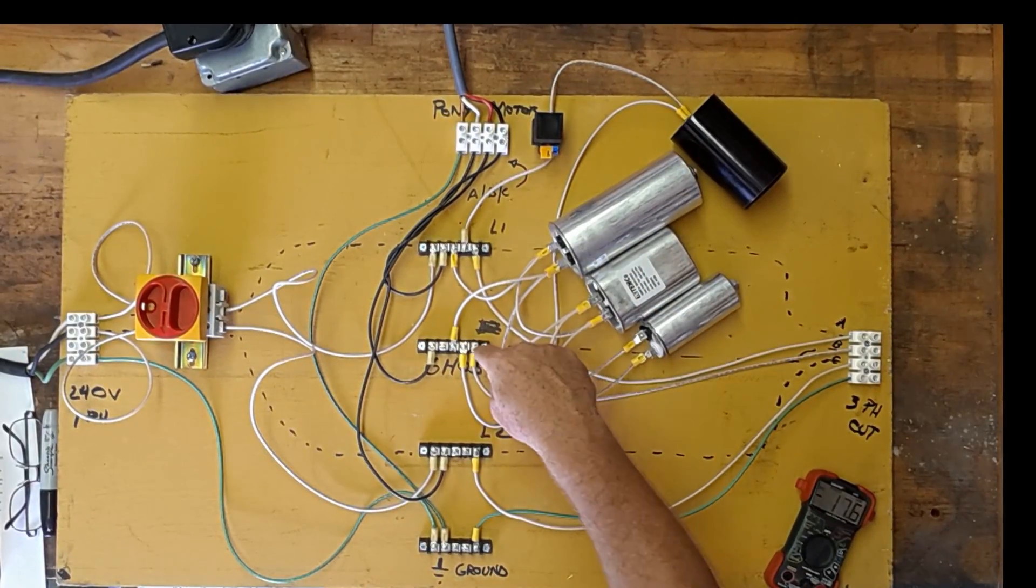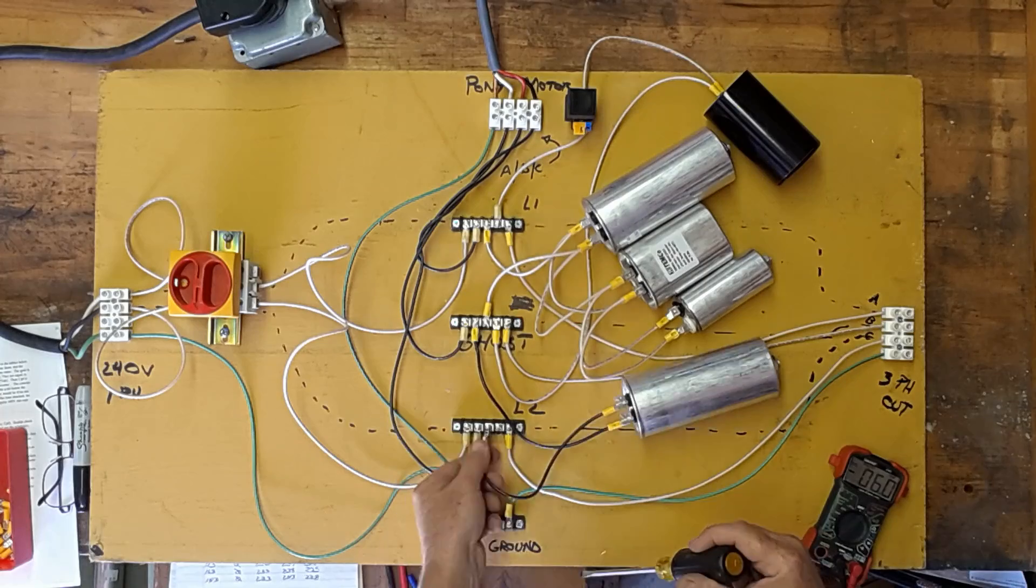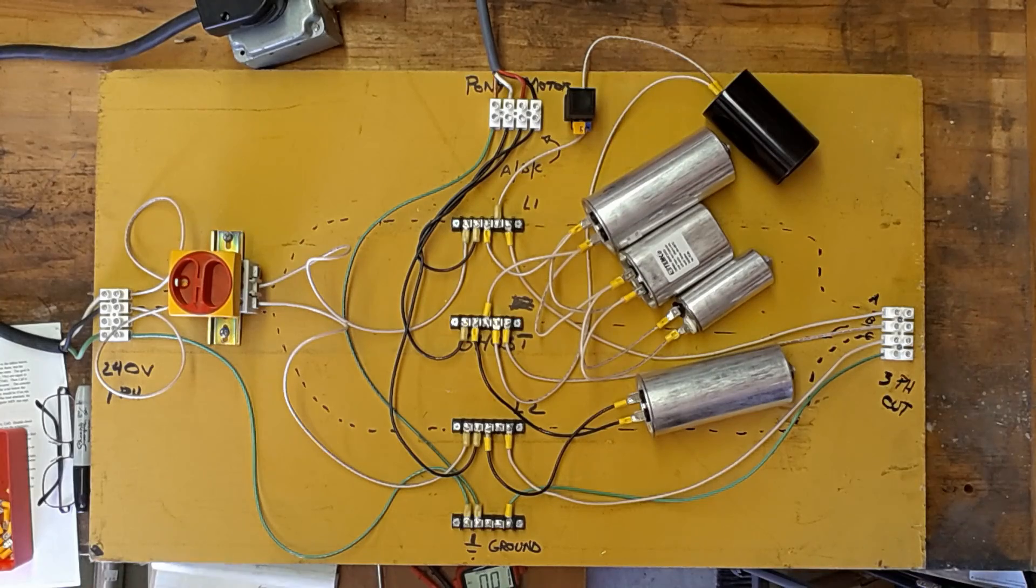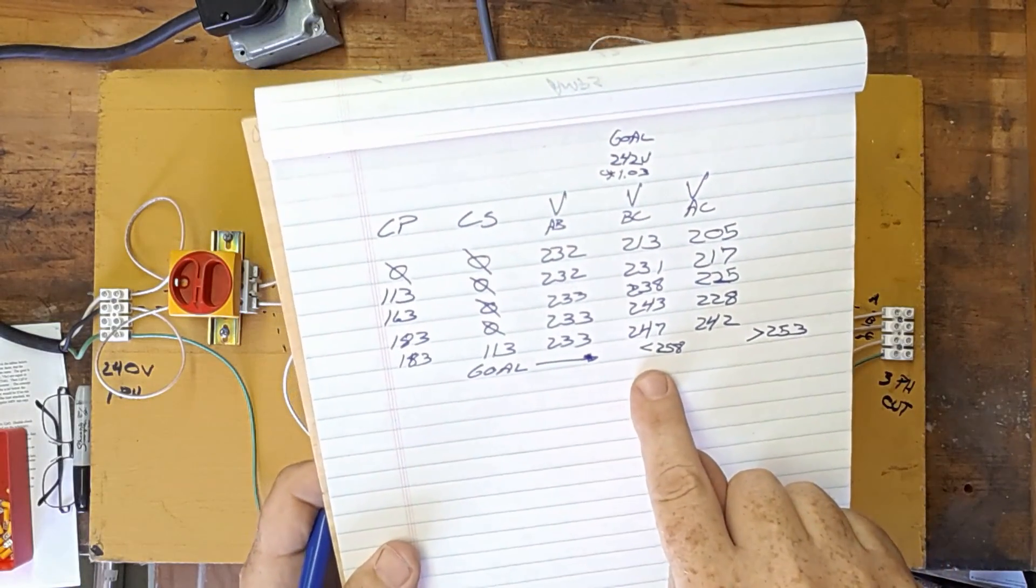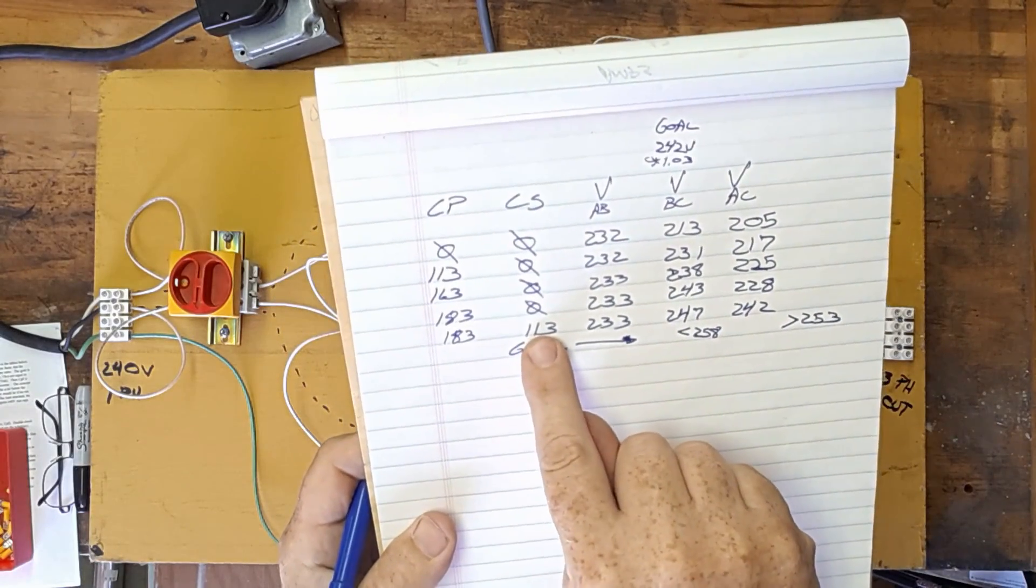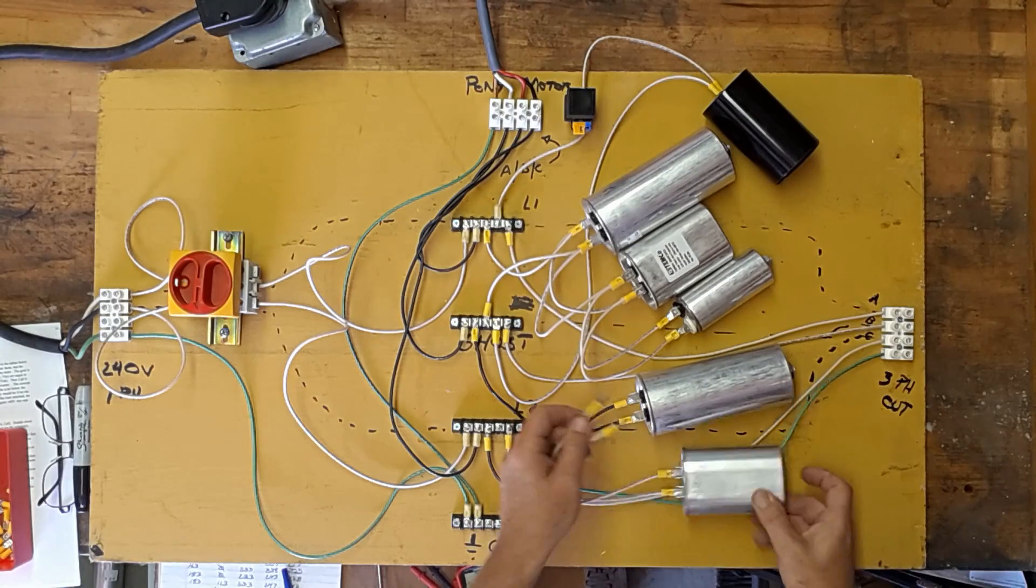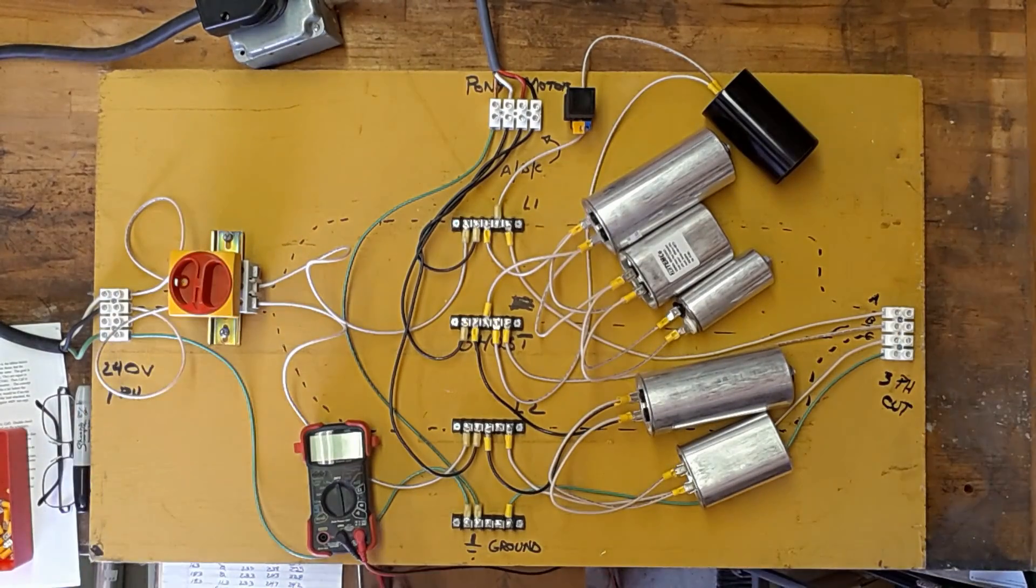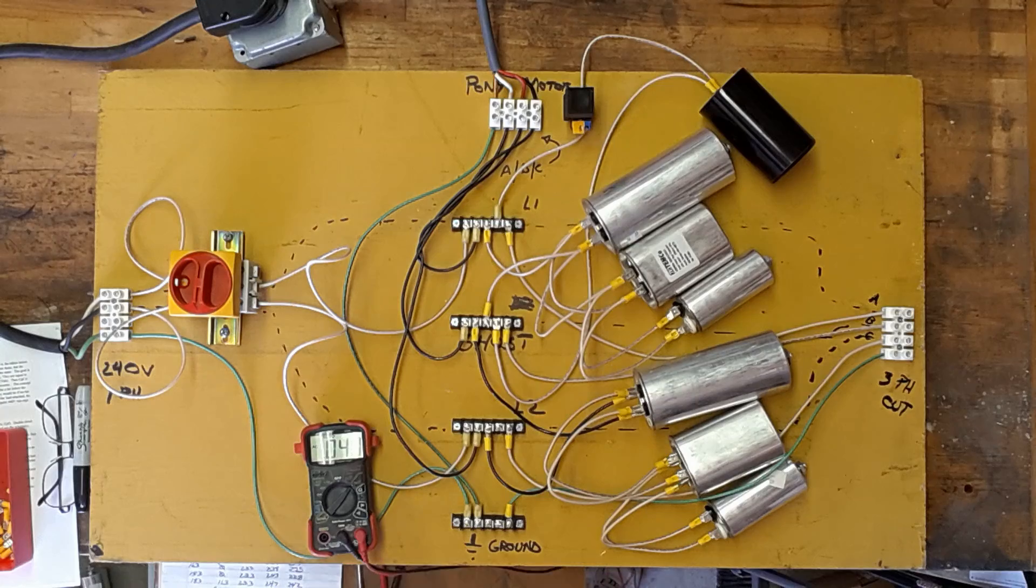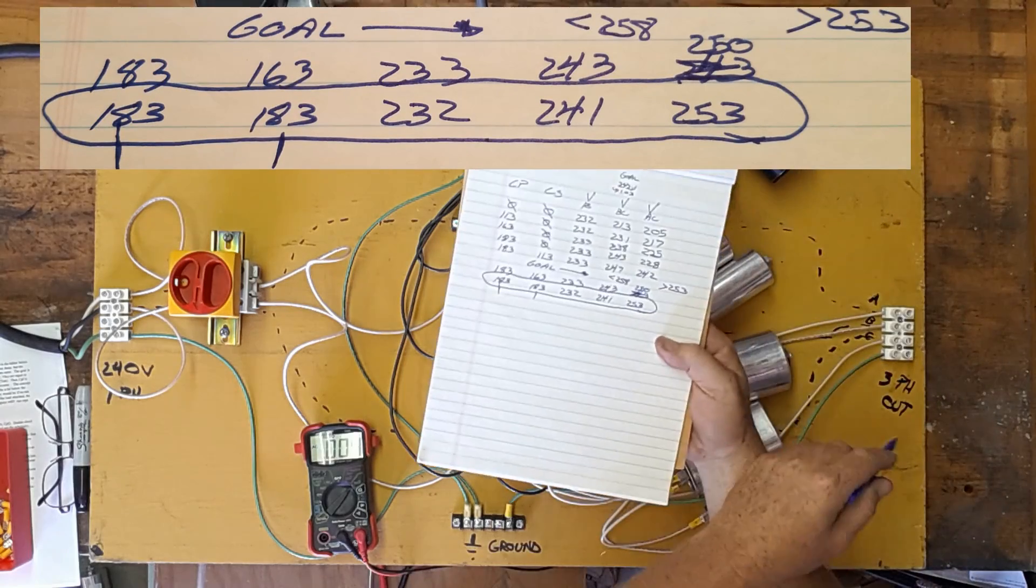So let's start again. This is our goal now. BC should be less than 258 volts. AC should be greater than 253. We just added 113. And you can see we're coming up. Let's add some more. We're going to add a 50. Again we're going to add them in parallel. One more. There's our capacitors. Here. Our second set of capacitors here. And our voltages there.